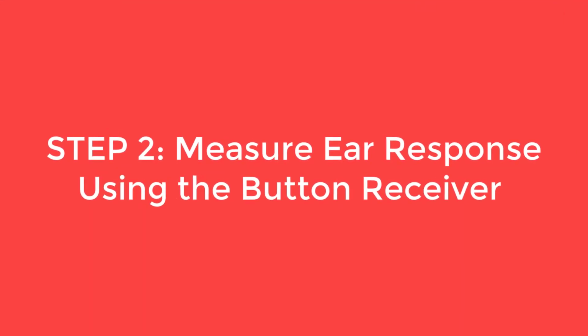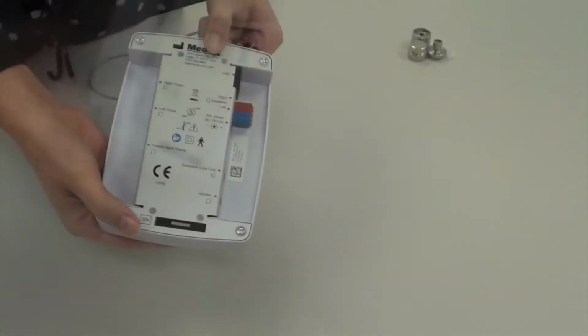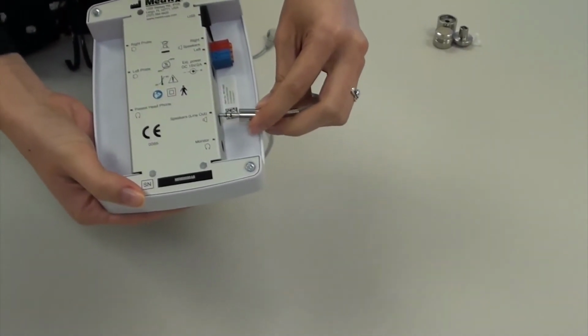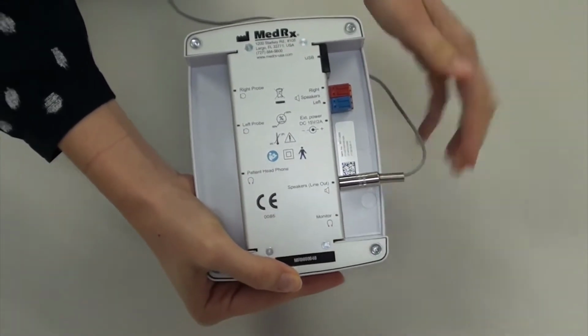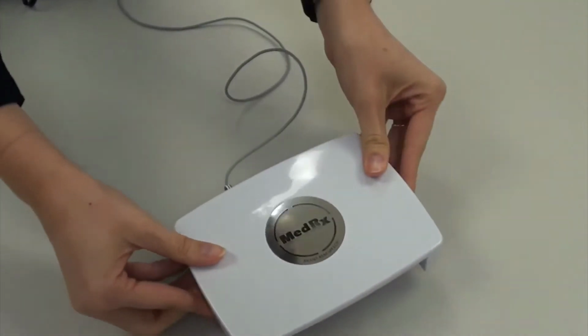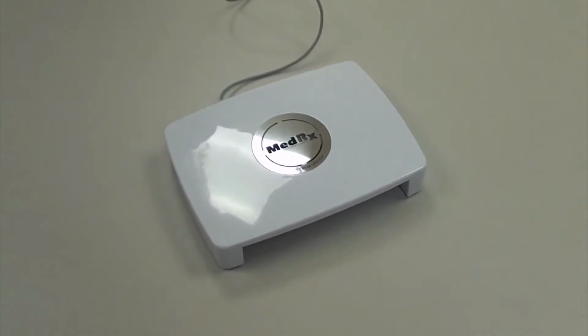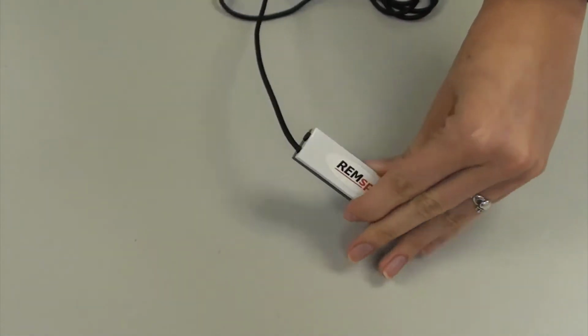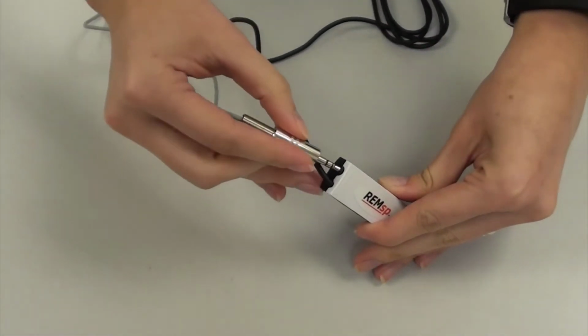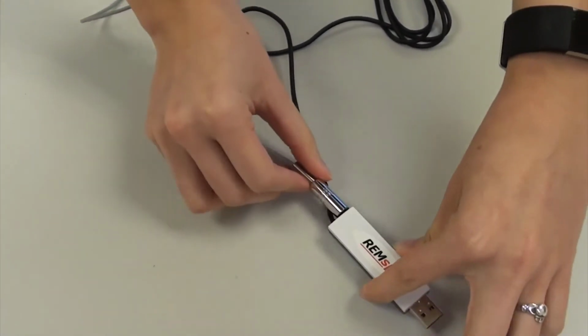The second step is to measure the ear response using the button receiver. Plug the button receiver into the port labeled speakers on the REM Plus or ARC system. For the REMsp, plug the button receiver into the speaker port located on the base of the hardware.